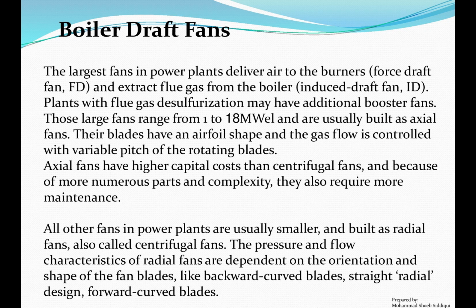Axial fans have higher capital costs than centrifugal fans, and because of more numerous parts and complexity, they also require more maintenance. All other fans in power plants are usually smaller and built as radial fans, also called centrifugal fans. The pressure and flow characteristics of radial fans depend on the orientation and shape of the fan blades, like backward curved blades, straight radial design, forward curved blades.